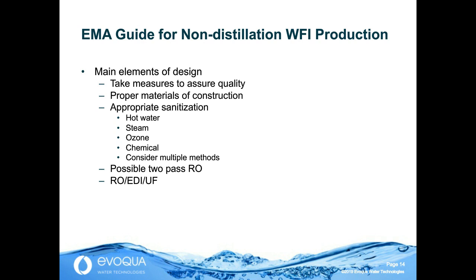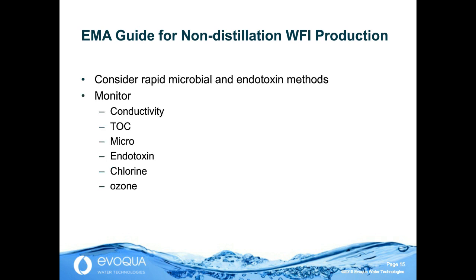It mentions consideration of 2-pass reverse osmosis, but does not require it, and expressly states that a system such as reverse osmosis, electrodeionization, ultrafiltration could be appropriate. It recommends consideration of rapid test methods for micro and endotoxin and significant monitoring, which makes sense in systems of this type: conductivity, TOC, possibly micro and endotoxin rapid, but certainly, of course, done in the laboratory, if not rapid or both, and chlorine and ozone if they're used. So those are considerations for construction.